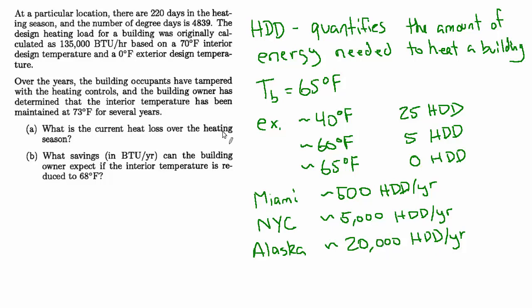But coming back to this specific problem, we've been told that there are 4,839 heating degree days and that the heating season is 220 days long. So we can figure out the average delta T. All we have to do is take the 4839 heating degree days and the units are degrees times days and divide by the number of days, which is 220. Days cancels out and we get 22 degrees. That's the average delta T throughout the heating season.